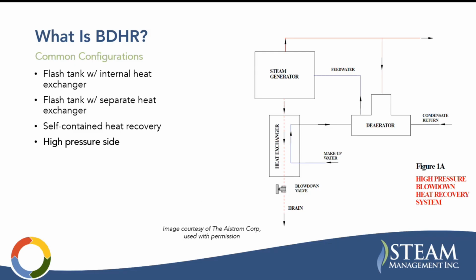And then the last one I'll mention, and this is not an exhaustive list, but these are just some common ones that I've seen. This is a high pressure side heat exchanger. The difference here is that you are putting your heat exchanger upstream of this blowdown valve. So before you drop pressure and let your blowdown flash, you're putting it through a heat exchanger, going liquid to liquid. The advantage here is that the blowdown is hotter, so you have a larger temperature difference to work with. The disadvantage is that it's a little bit more complicated because you might be within your boiler code limits, and so the materials of construction would be more stringent. But yeah, it's another option.